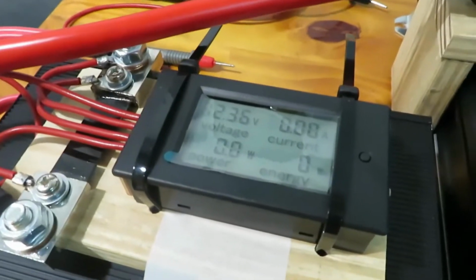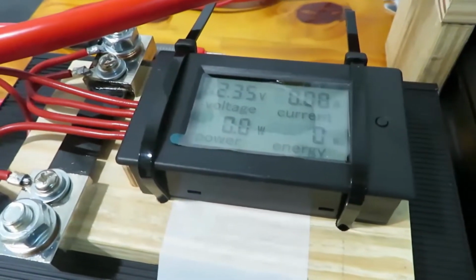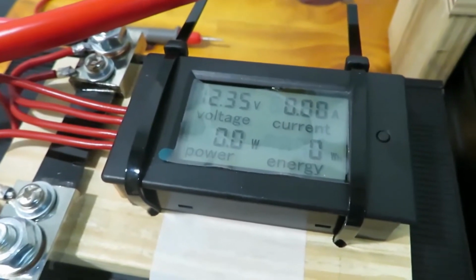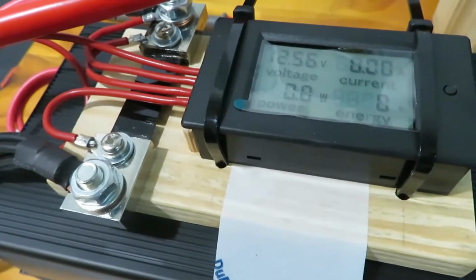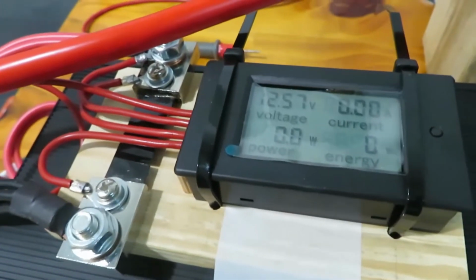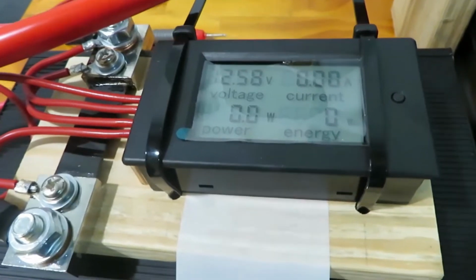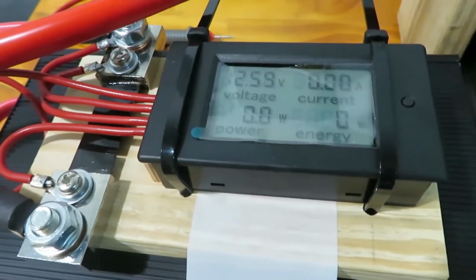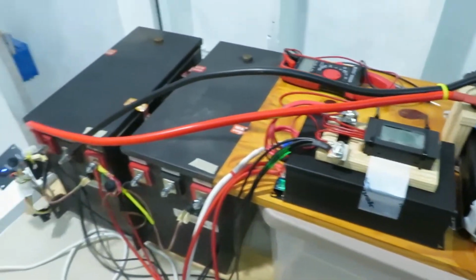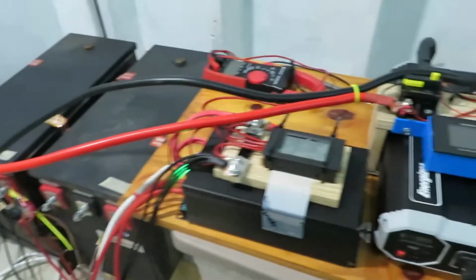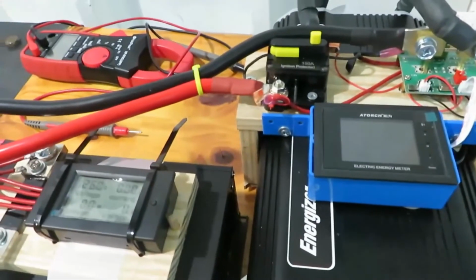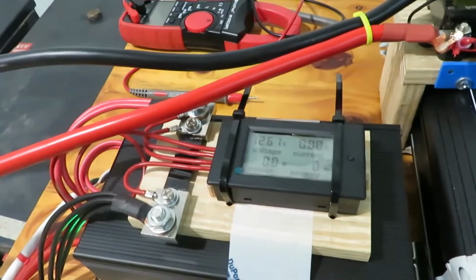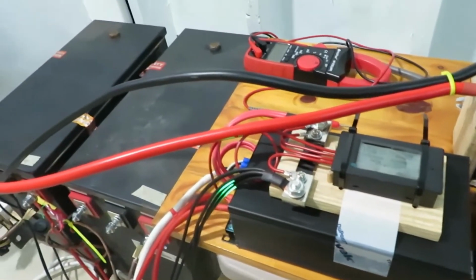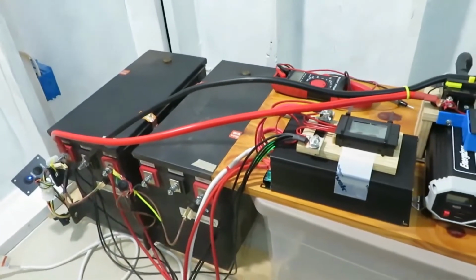So now the voltage is 12.35. This is the, oh, it just tripped, I believe. Yes, it just tripped. So it tripped at 12.35, but the battery voltage rebounds back to 12.58. So it's good that we captured the tripping. So I'm going to wait for an hour for the battery voltage to settle and then come back to measure the individual cell voltages and also start the recharging process. See you later.